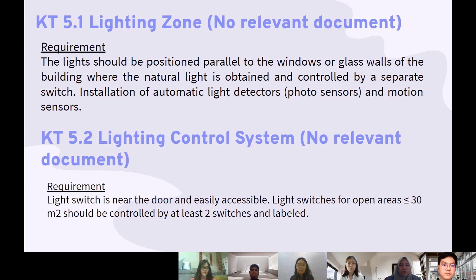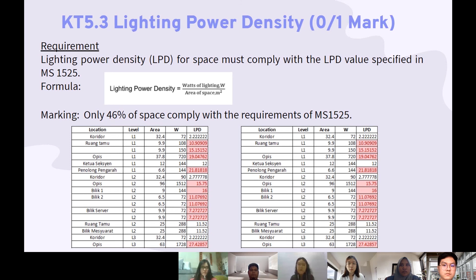Next. KT 5.3 is about lighting power density and it must comply with the value specified in MS1525. The maximum LPD value for general office is 12, and it is found that only 46% of the space in Block B met the requirement. Therefore, 0 mark will be given. Next. For KT 6.1, coefficient of performance, the COP needs to be according to MS1525, and I found that 9 units out of 22 units of air conditioners have a COP that does not meet the requirement, which is 2.93.